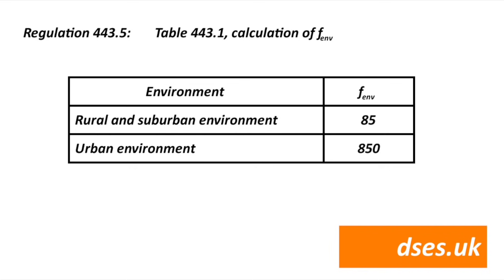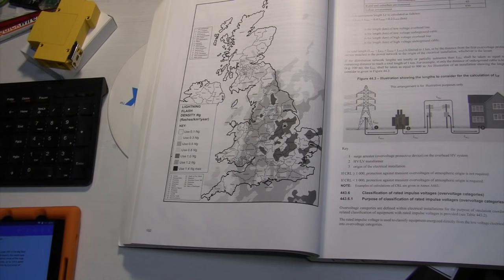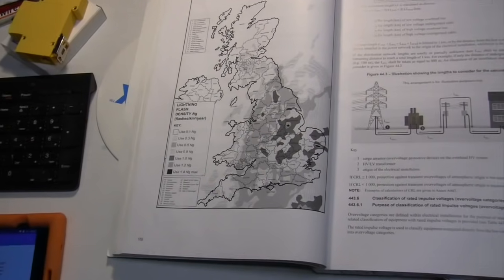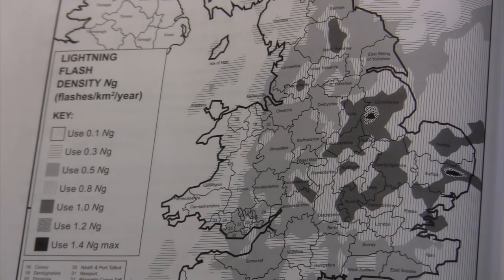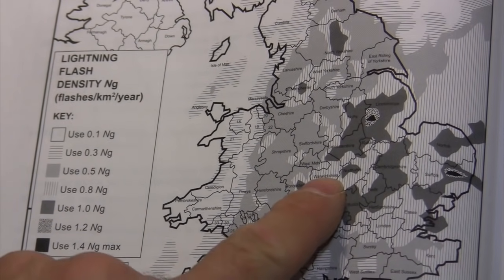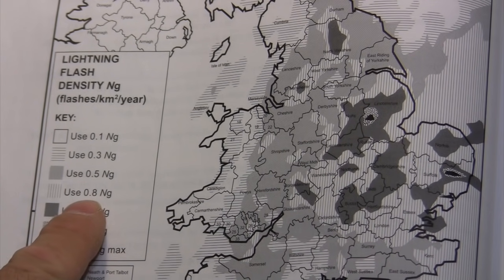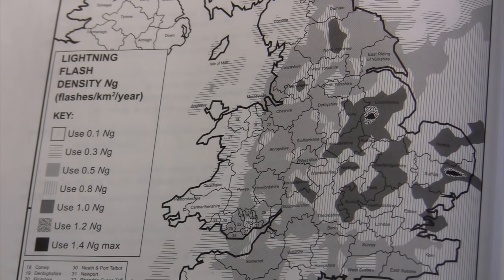So far so good. Let's skip then to NG, the lightning ground flash density. We can find that on page 102 of the Big Blue Book. This map shows us the lightning flashes per square kilometre, and as you'd expect, the southeast has a higher density of lightning strikes than up north, as indicated by the darker areas of the map. It varies from a factor of 0.1 for areas with a low volume of thunderstorm activity up to 1.4 in some parts of Suffolk and Lincolnshire. Where I am here in Warwickshire, I can see that NG is a factor of 0.8. Lovely stuff. All I need now is LP.